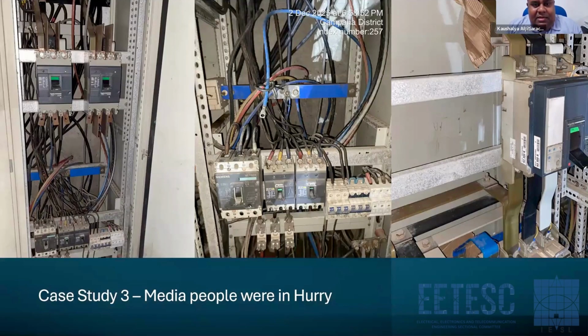This was a media station. They were in a hurry to print their newspaper, but just look at the distribution board. These breakers were wet when we visited. If you see, water is still inside. No cleaning has been done. The stain is there on all the arc chutes. Just see the deposits. Here you can see wetness, and on these arc chutes you have wetness. Here you have residual water.